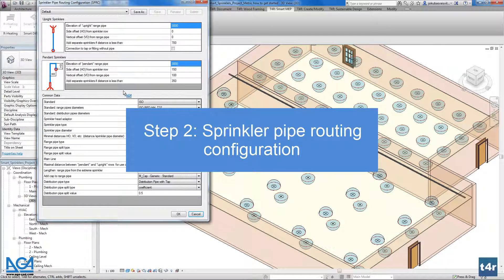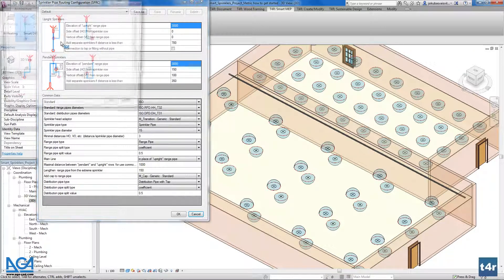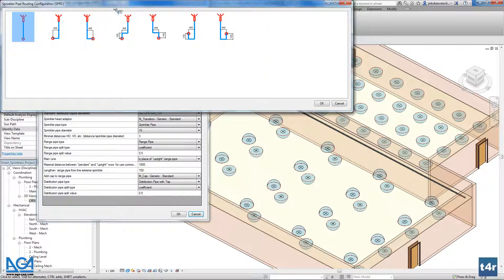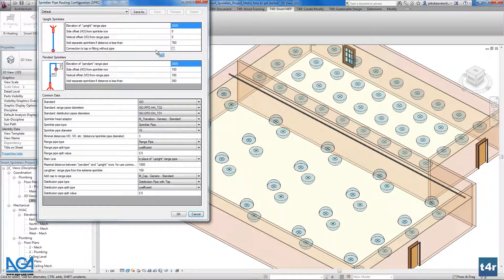In the routing configuration, firstly we have to define what kind of connection we will use for upright and for pendant sprinklers. Here we have images that we can double-click to find the most popular connections and use any of them. We can also define the elevation of the upright range pipe and the pendant range pipe — for example, three thousand millimeters, which is three meters.